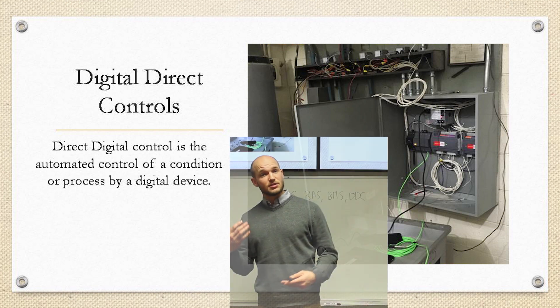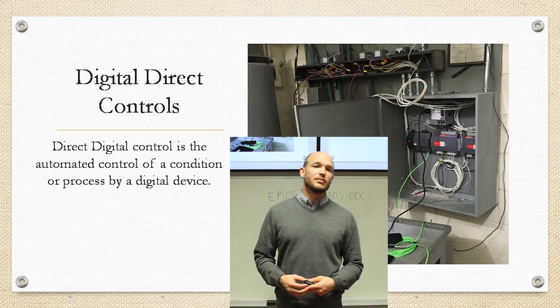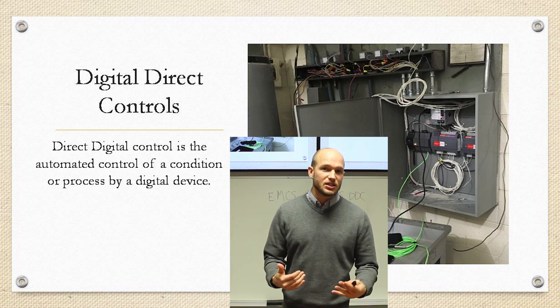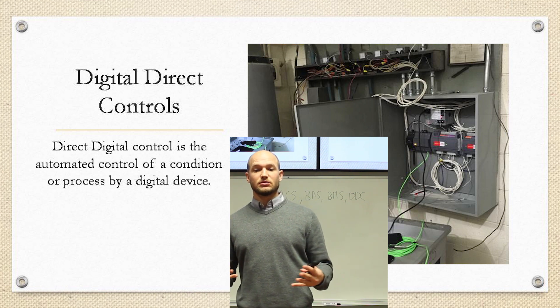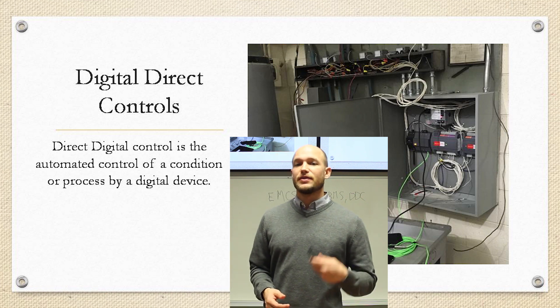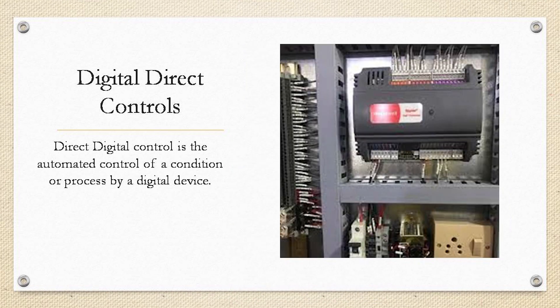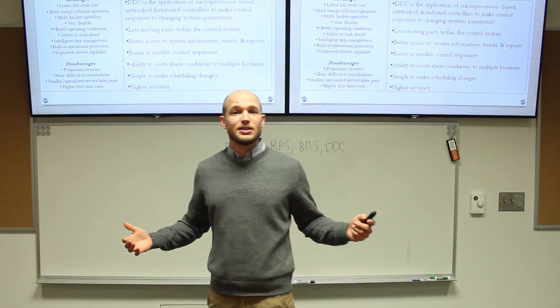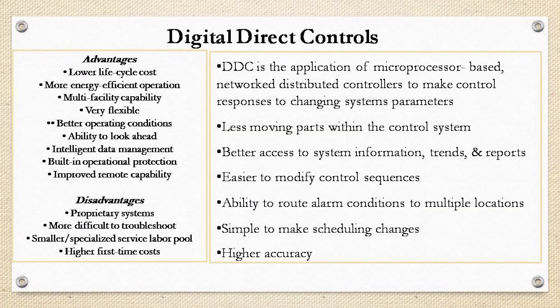The last type is DDC — Direct Digital Controls — the latest and greatest. Advancements are still being made with DDC protocols. In essence, DDC is replacing pneumatic and electromechanical controls — this is what's being installed right now. The advantages list for DDC is longer, but there are also some disadvantages: you're getting into more technical territory, there's training required, and new software packages to learn. But this is where the industry is heading.